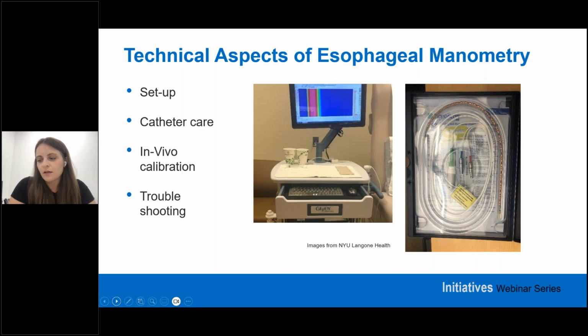the issue. The Medtronic software tells you which sensors are failing after the catheter doesn't calibrate. So then you can either block that sensor or speak to the physician and talk to them about how comfortable they are with using a blocked sensor during the study.